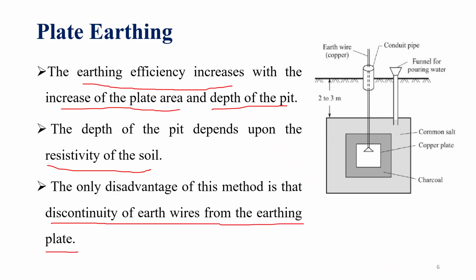Generally, we are placing the earthing plate at the bottom of the pit and we are going to completely enclose that with charcoal and common salt, up to the ground level. So, we are not able to see whether the earth wire is still connected to the earth plate or not. Sometimes the connection may be broken. That is the only disadvantage with plate earthing. Okay, this is plate earthing.